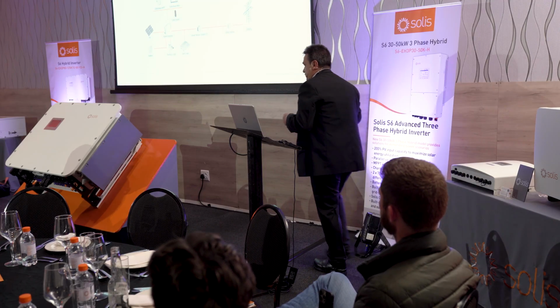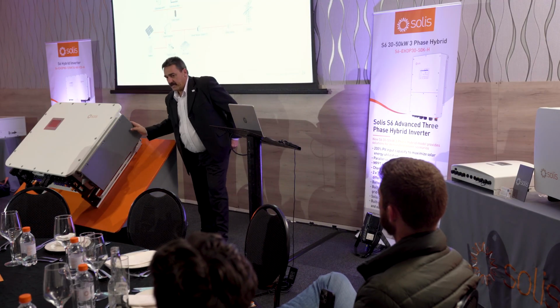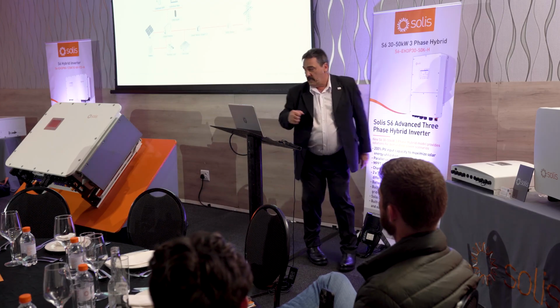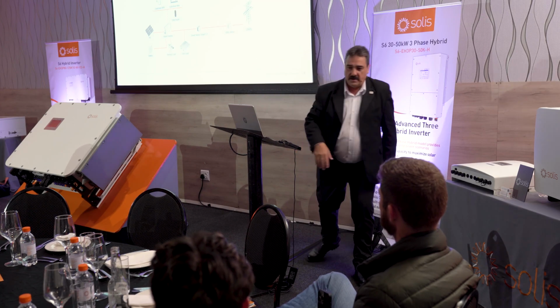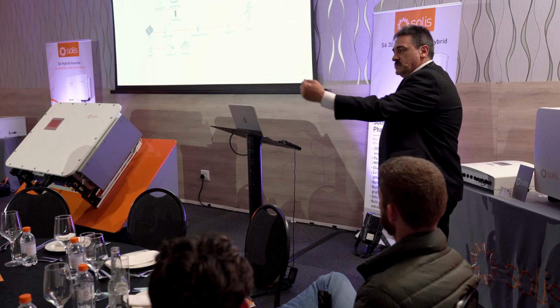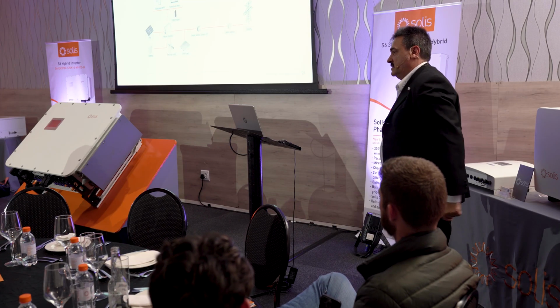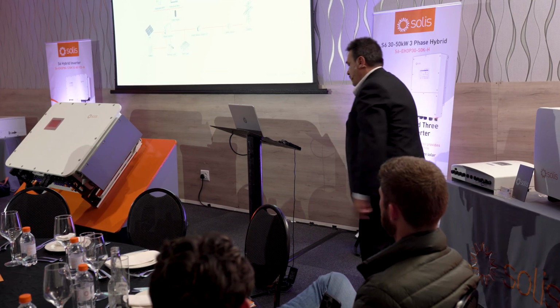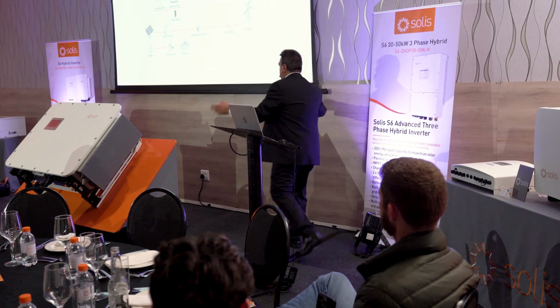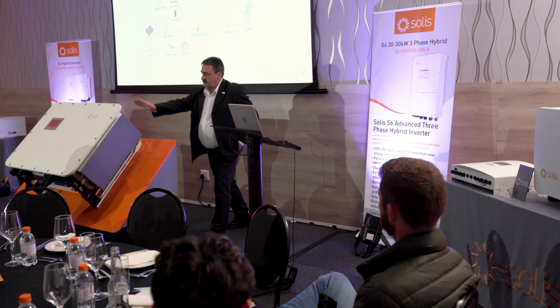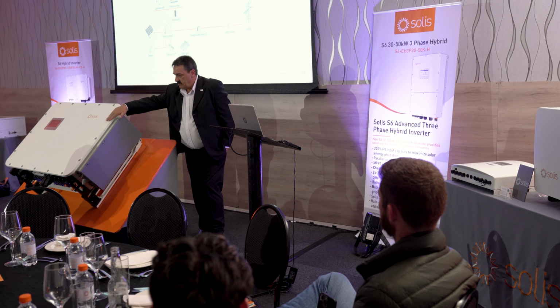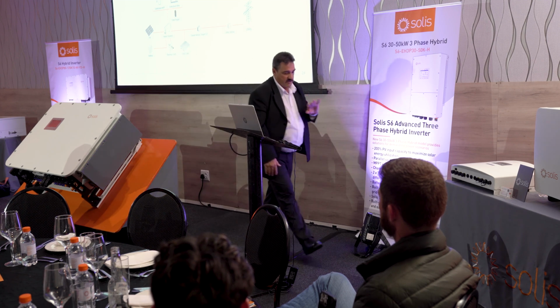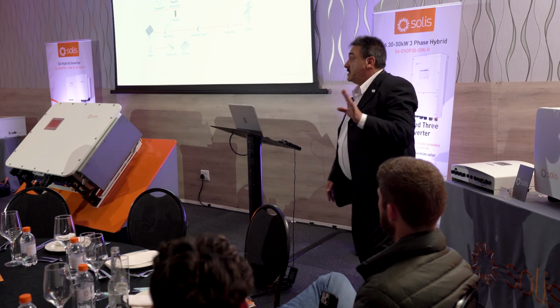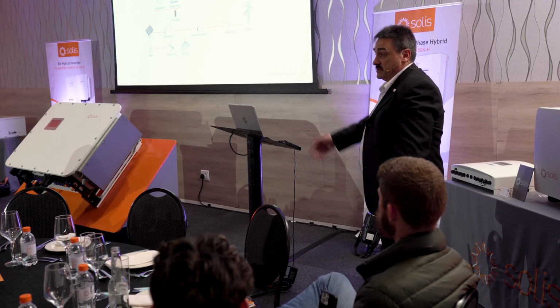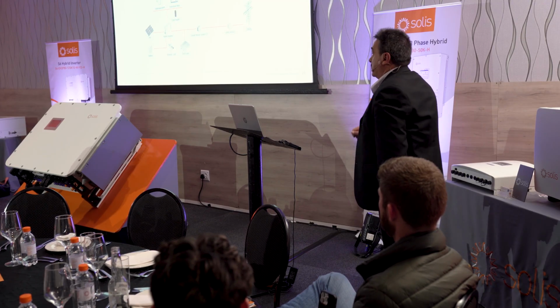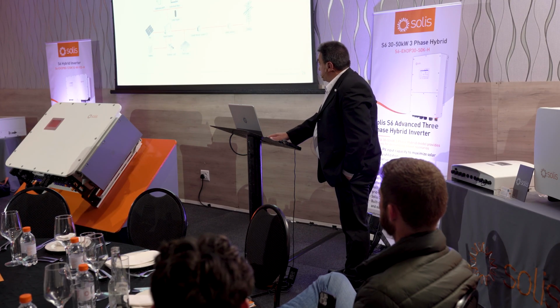So in a lot of places you might install this, the council comes back to you and says, yeah, okay, that's very borderline. We're going to restrict the amount of power you may sell back to the grid, because of the infrastructure that's available or existing. And then you can set it. At no point in time do we want to send more than 10 kilowatt an hour back to the grid. This is the function and the setting that you can just set. So it makes provision for all of those things.